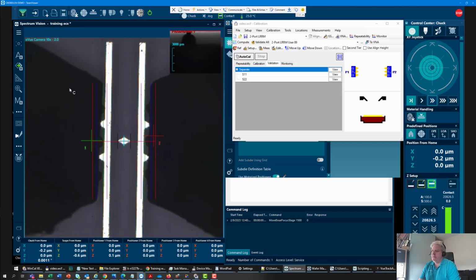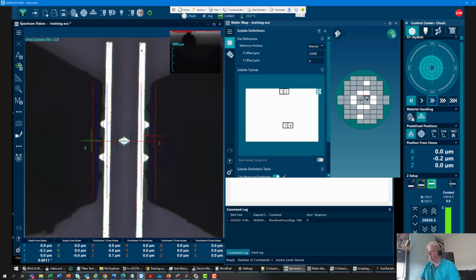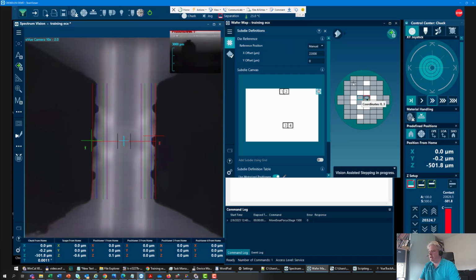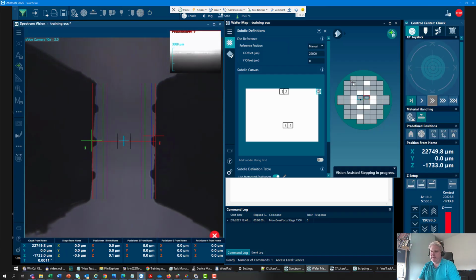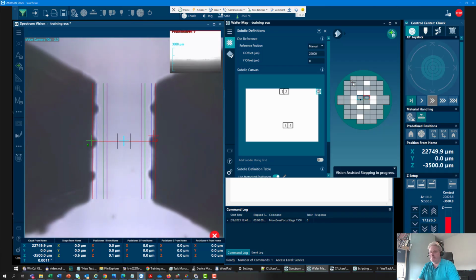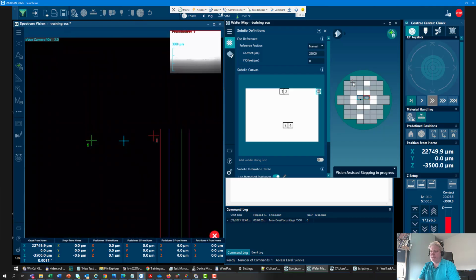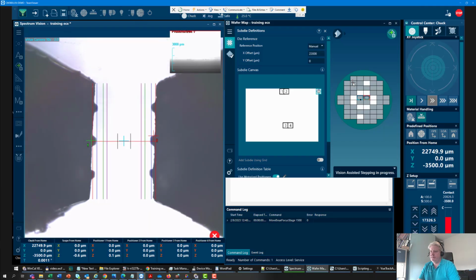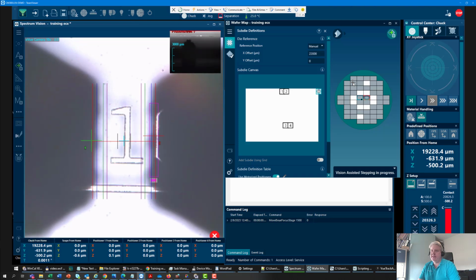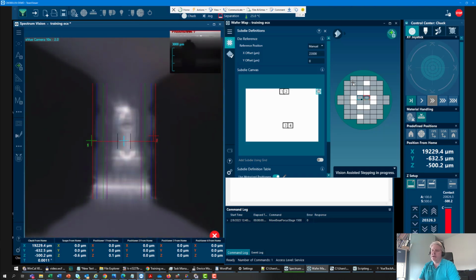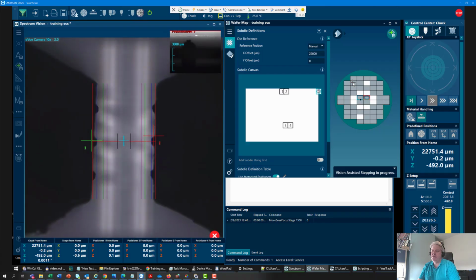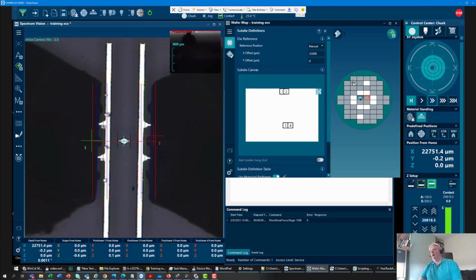So now we can go and check it out, just check everything looks accurate. I should be able to go in the wafer map and step to a new location. That's going to do optical correction from stepping from one site to another. Look for the probe spacing, probe position in space. It doesn't actually look for over travel, but it's there by virtue of the known offset from the fiducial to the reference location. Yeah, that works pretty nicely. And what else we can do is we can do AutoCal.